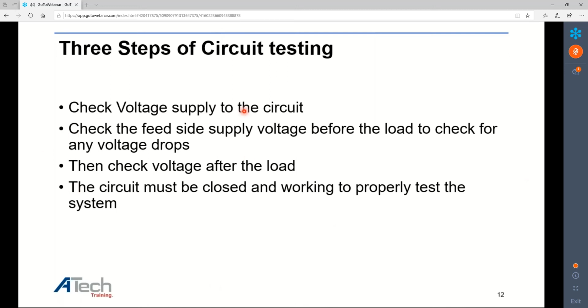First, I have to check my voltage supply to the circuit. That might be my fuse, that might be right at the battery. I need to check the supply voltage before the load and check for any voltage drops. I'm allowed a couple of tenths, depending on how many components I've gone through on my circuit. I'm not going to have full source voltage if the circuit is live and working, so keep that in mind.